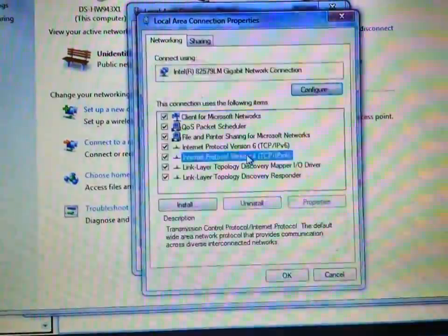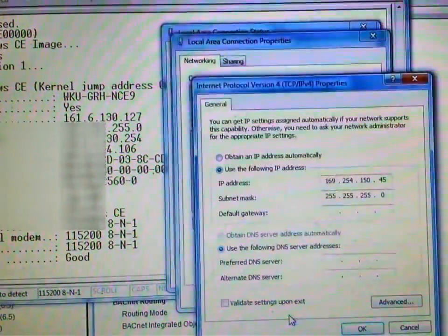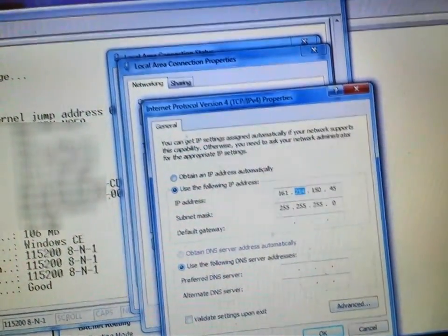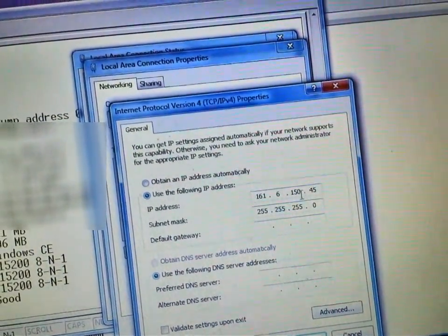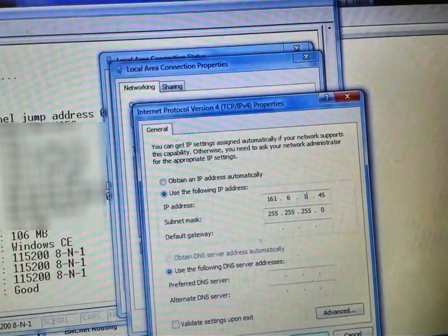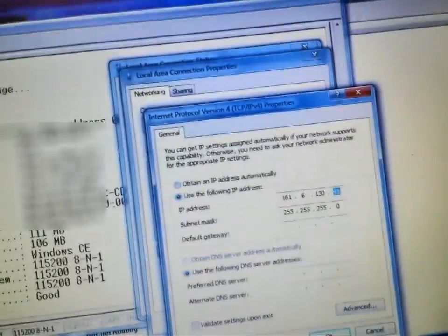Double click on this one here, and you will need to set your IP address for your laptop within the same range as the IP address of the NAE or NCE. If you don't do this, you will not be able to gain access to the device. So once you have that information entered here, you should be able to browse into the configuration screen and set up your device.